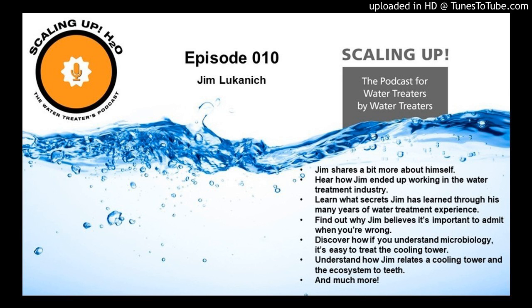So yes, and to go to your point one step further, if people can control the biofilm in their cooling water systems, everything else, the corrosion and the deposition from mineral deposits or scales, will follow suit typically. In most HVAC type cooling, if you get into higher temperature systems, you have some other phenomenon at the tube wall water interface or the heat exchanger water interface to deal with. Certainly in most systems that are relatively cool as far as heat load goes, microbiology plays a major role in all types of deposition.